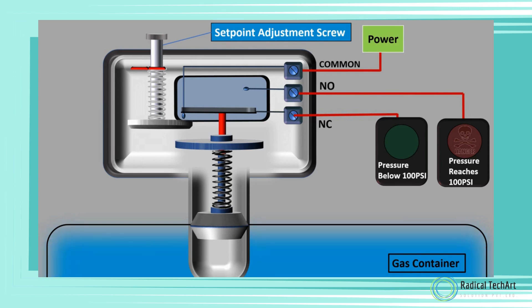The inlet pressure from the container is applied to the bottom of the operating piston, and during normal operation when the pressure inside the container is below 100 PSI, the normally closed circuit will be powered and green light will be on. We had already adjusted the tension of the range spring using setpoint adjustment screw so that it gets compressed when the inlet pressure reaches the setpoint.